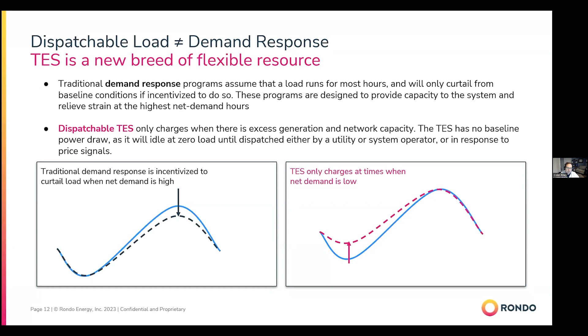To pivot for a moment, I'll close with a brief mention of another utility value proposition with a different flavor for electrified thermal energy storage, maybe a bit more similar to the Westinghouse solution we just discussed: steam power plant retrofits. Because the thermal energy storage design that Rondo and other technologies are pursuing has flexibility with respect to heat delivery, we can design boilers that directly match the steam conditions of essentially any steam power gen cycle. By charging with excess electricity on the system and then delivering steam to existing steam turbines during periods of higher demand, thermal energy storage becomes electricity to electricity storage as well, with round-trip efficiencies limited to the physics of a Rankine cycle.